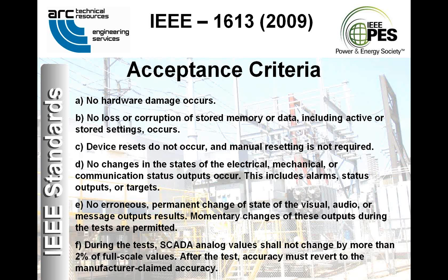IEEE 1613.1 extension to 1613 has a couple of other unique features. Communications cards inside smart meters will now be assessed using the IEEE 1613 acceptance criteria we just went over. The meters themselves were covered under ANSI C12.1, but there was no coverage of the cards, so this eliminated that gap.